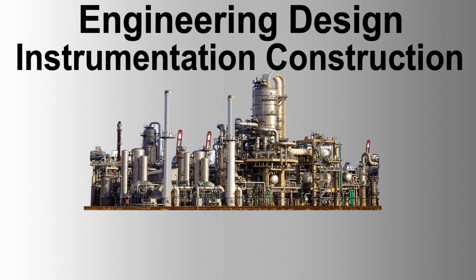Testing. A comprehensive testing program shall be implemented to verify the functionality and performance of all instrumentation and control systems. The testing program shall include loop testing to verify the correct operation of individual instrument loops, functional testing of control systems and safety interlocks, calibration of instruments to ensure accurate measurement and control, performance testing to verify that systems operate as intended under all expected operating conditions. Detailed test procedures shall be developed and submitted for approval.